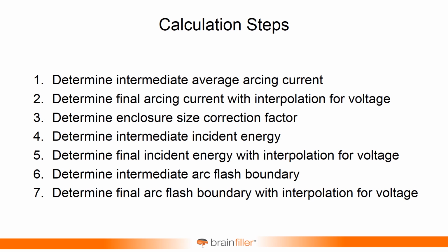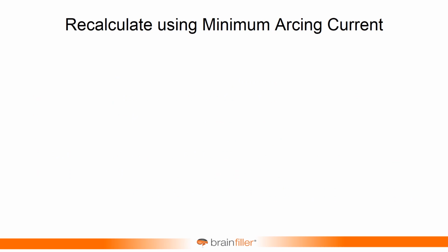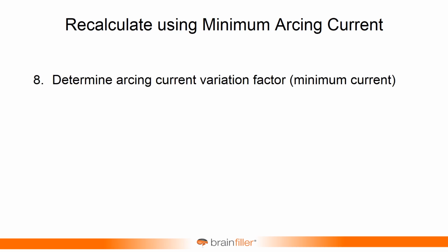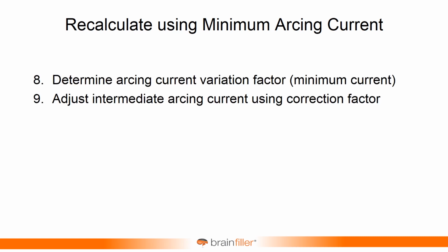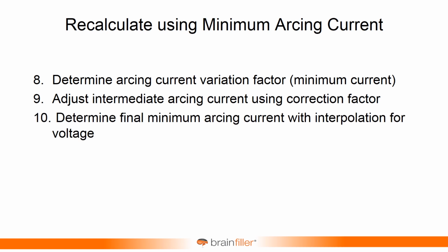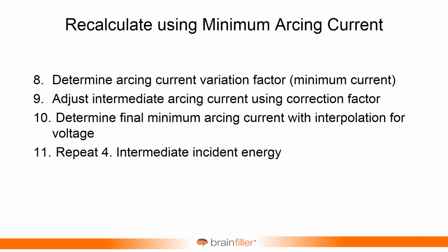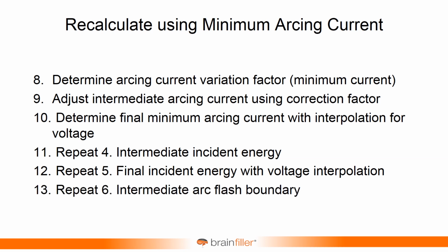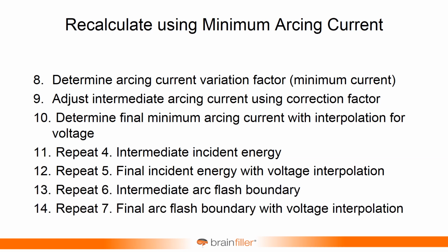And then you go back and you calculate the adjustment factor, the variation factor, to determine the minimum arcing current. So then you adjust the intermediate, not the final, you adjust the intermediate arcing current using the correction factor, and then go back and redetermine the final arcing current with the interpolation. And then you go back and recalculate the intermediate incident energy and the final incident energy and the intermediate arc flash boundary and the final arc flash boundary.